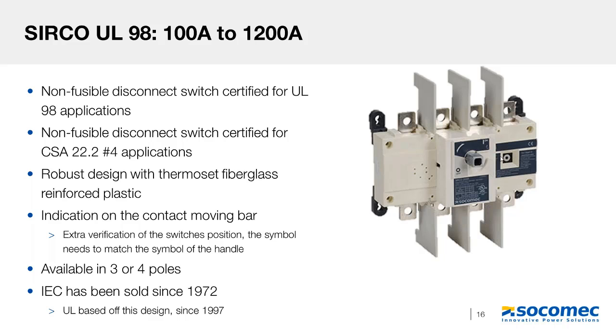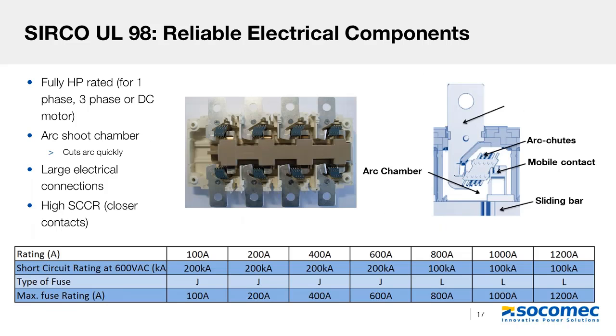So if it has this O, which is off, then the handle should also be in the same position. If the handle is not, then you know that there's something wrong with the switch. Don't touch it. Don't try to do maintenance or anything, because it could still be on when it says it's off. So that's a really cool thing about the switch, that extra safety precaution. And then this switch has short circuit ratings of up to 200 kA. In this slide, you can also see our arc chute chamber. That just cuts the arc very quickly to, again, ensure the safety of people.